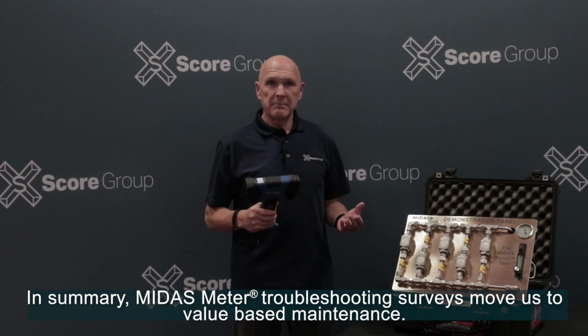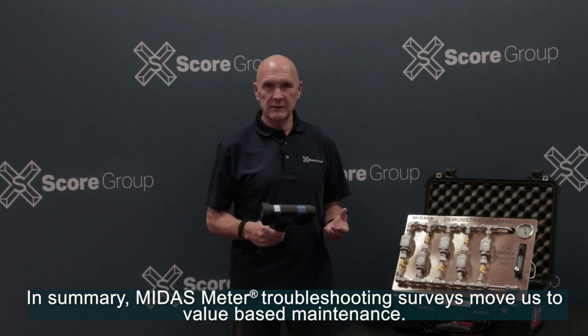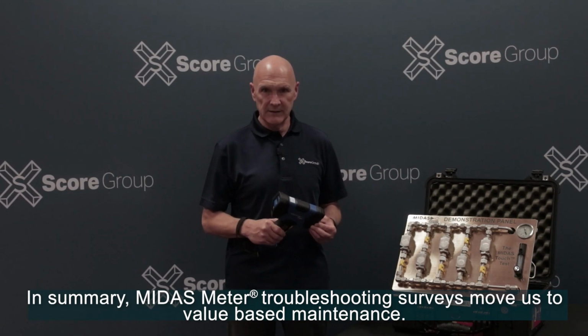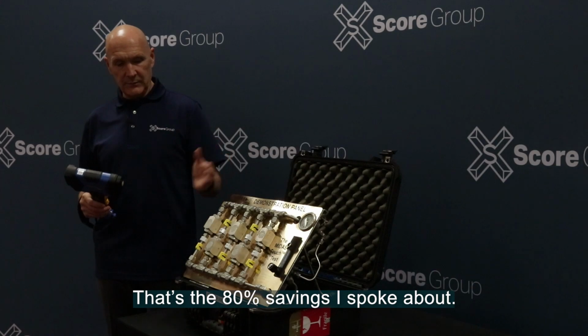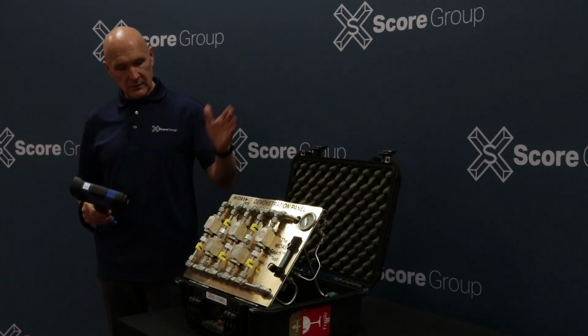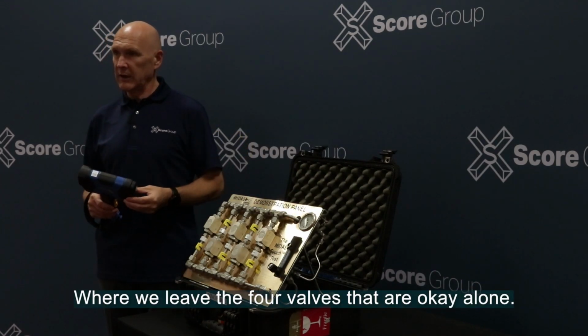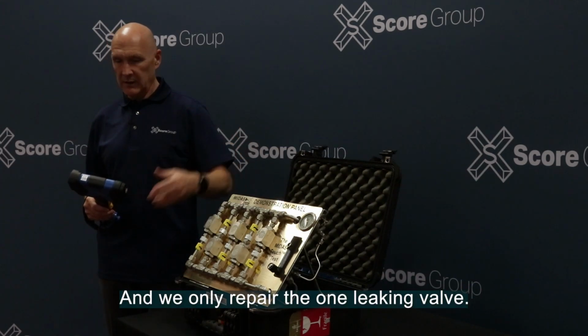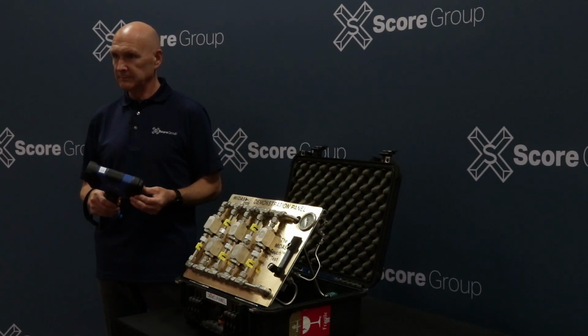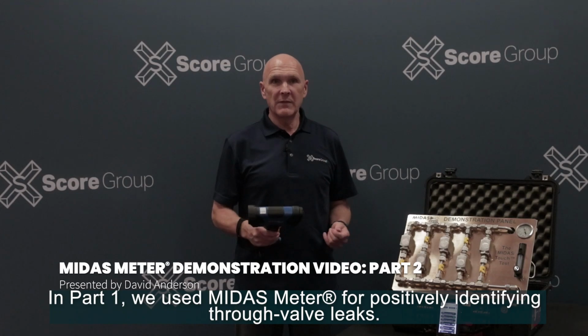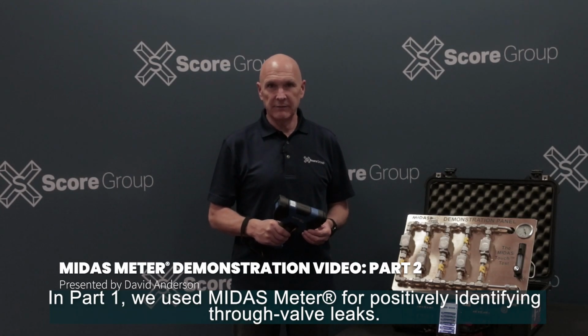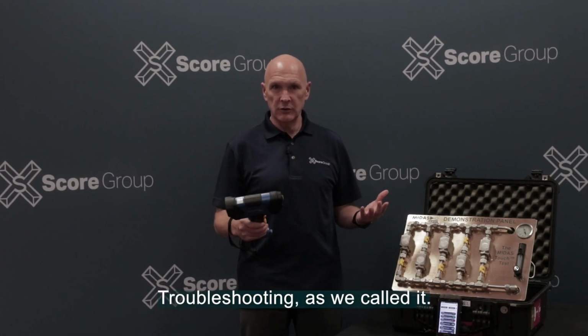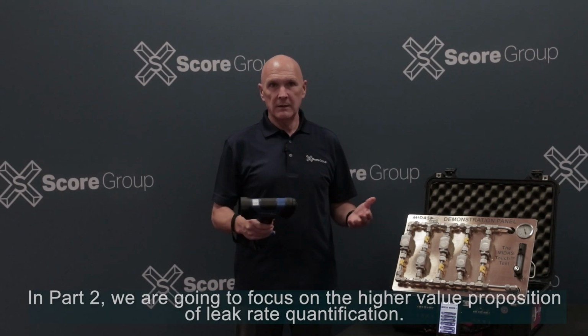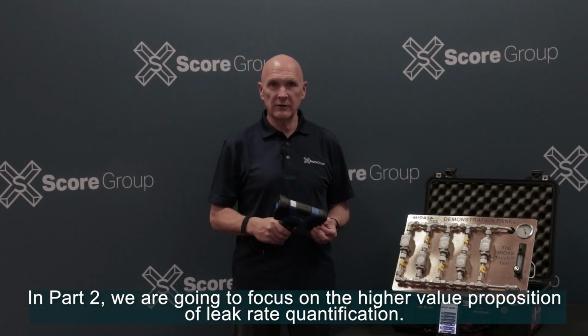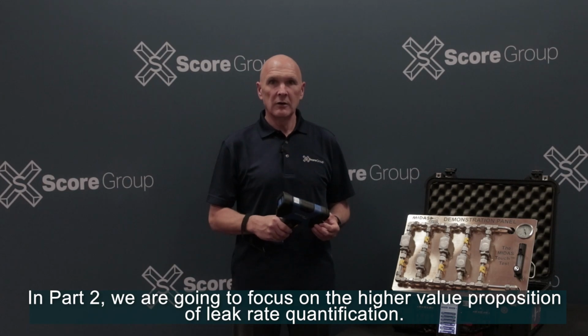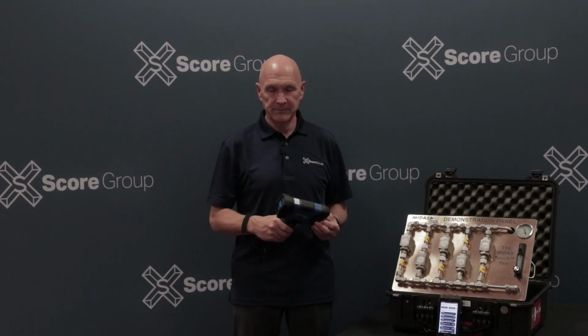In summary, MIDAS meter troubleshooting surveys moves us towards value-based maintenance. That's the 80% savings I spoke about, where we leave the 4 valves that are okay alone and we only repair the 1 leaking valve. In part 1, we used MIDAS meter for positively identifying through valve leaks, troubleshooting, as we called it. In part 2, we're going to focus on the higher value proposition of leak rate quantification.